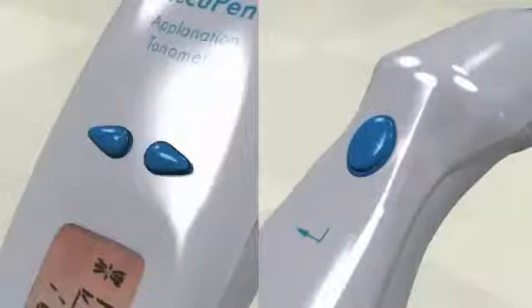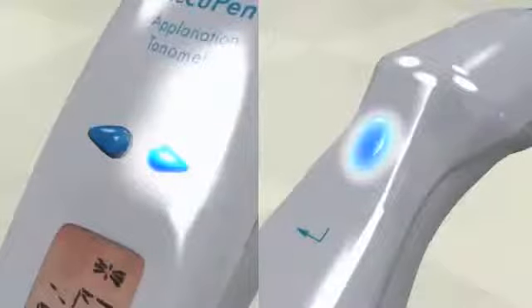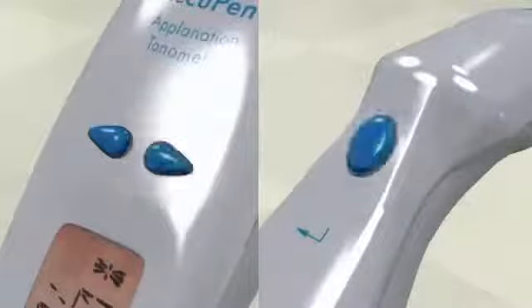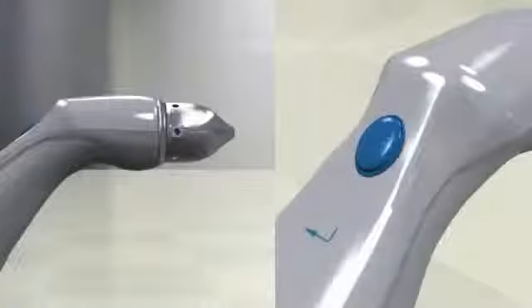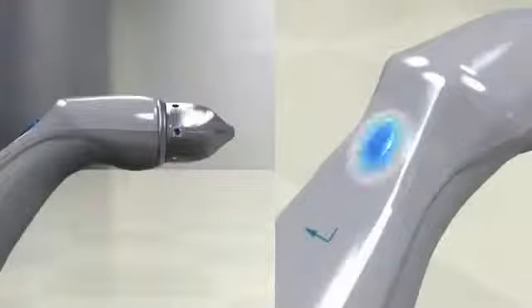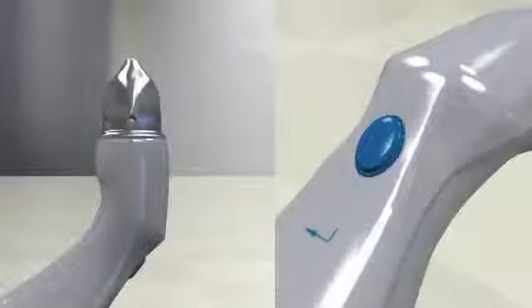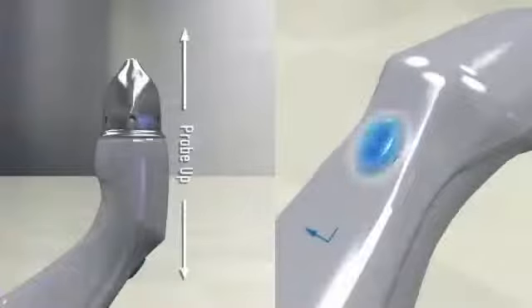When calibration is necessary, simply hold the up arrow and Action button simultaneously for 3 seconds until the probe horizontal display screen appears. Hold the transducer horizontal to the floor and press the Action button. The unit will chirp and display probe up. Hold the unit so that the transducer tip is pointed directly in the air and press the Action button. The unit will then chirp and display probe down.